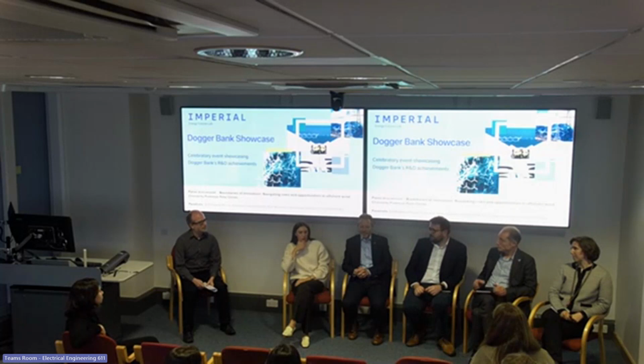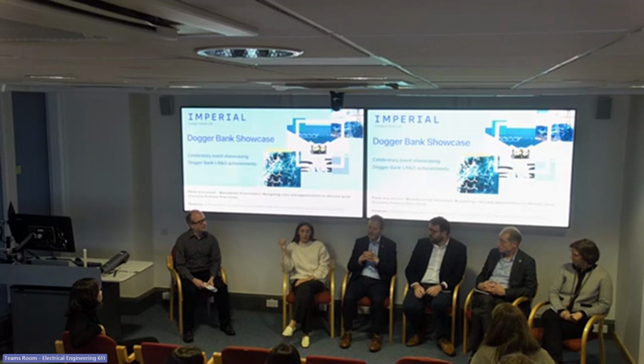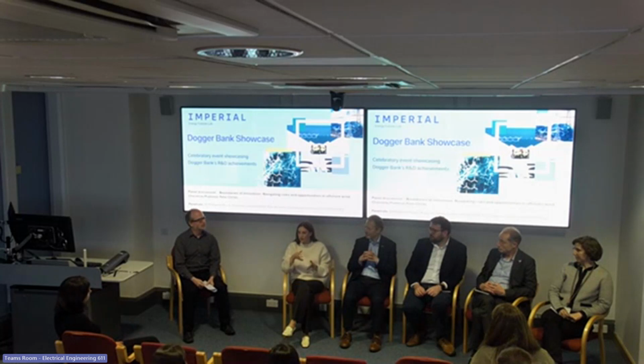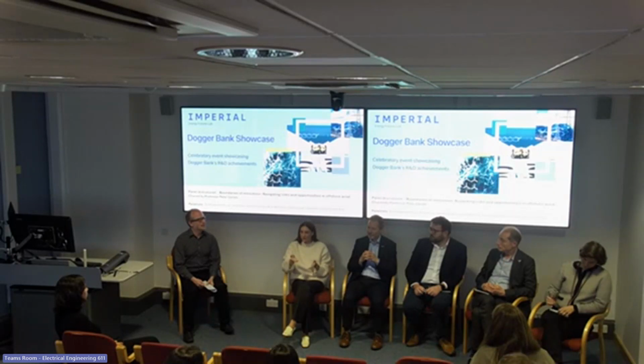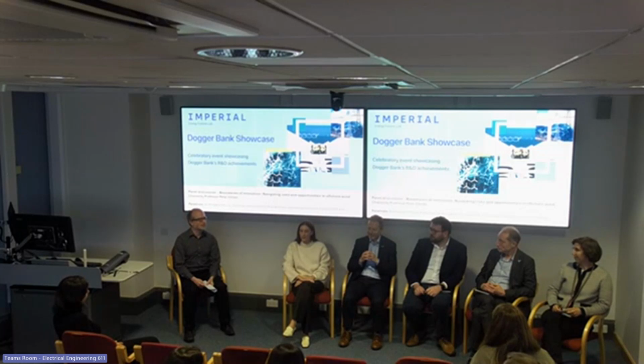So on the first one, regarding the services we're providing to the network, that's for Dogger Bank C, which connects to Lackenby substation. Because nuclear generation in that area was going to be phased out, National Grid developed the Pennine Pathfinder program, looking for new plants that could provide reactive power services. We raised our hands and said we have a fantastic converter that can provide the reactive power needed. That's the service we're providing to the grid, supporting voltage stability in the area however the network needs it. The last thing we need is the final connection to the national grid, but as soon as it's ready, we'll be there supporting the network.